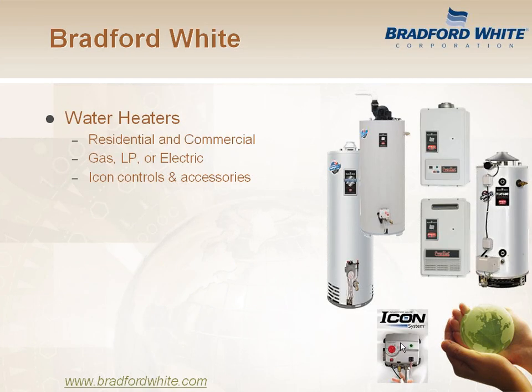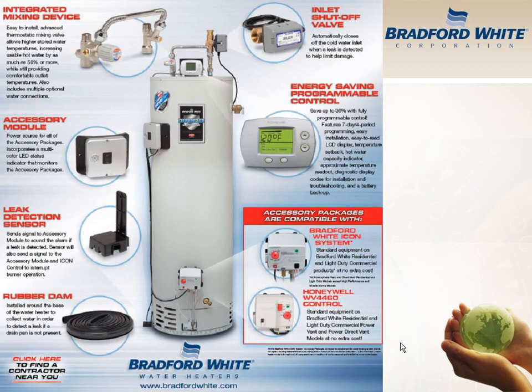We do handle Bradford White water heaters. Really hasn't anything to do with the boilers other than they pipe the same way. And there's nothing sexy about a water heater, I won't lie to you guys. But there is one cool thing that has happened recently, and that's the icon controls that are available for these guys. As you can see here, some of the accessories that are available now with this new icon gas valve that Honeywell makes for them is a setback thermostat. You probably have never had a setback thermostat on your water heater before. Now you can do that. It's a pretty cool feature.